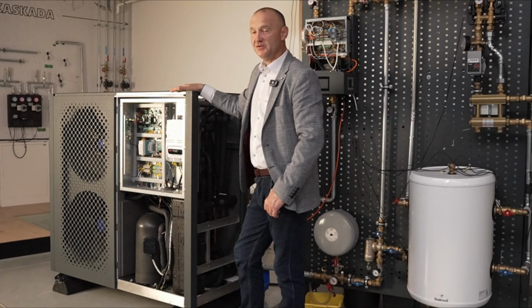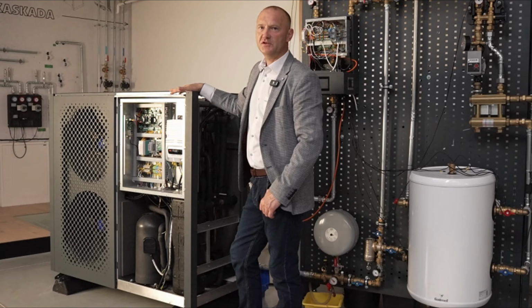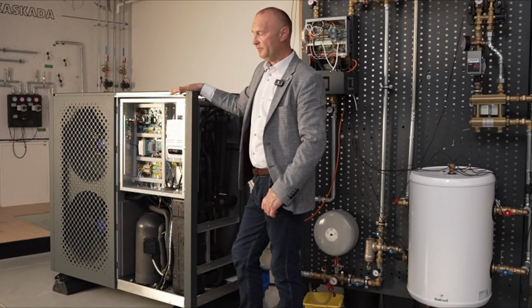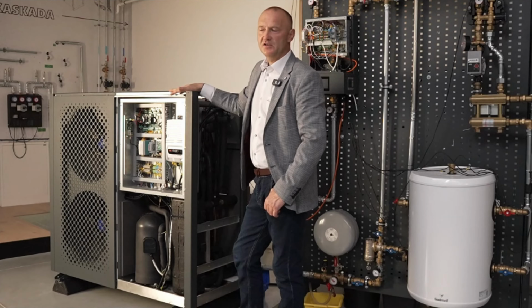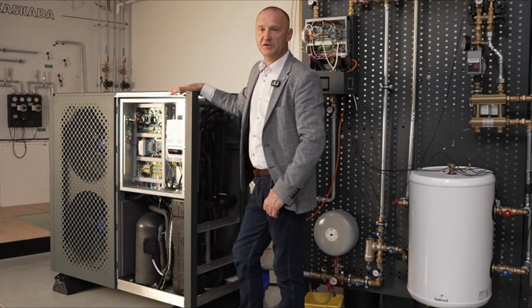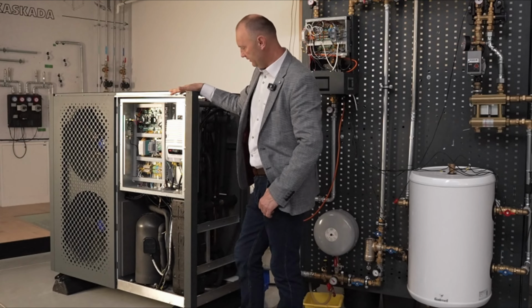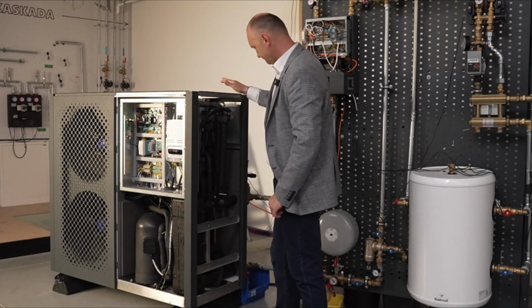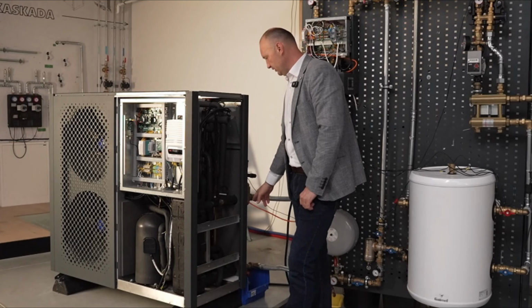And therefore, in our heat pumps, you can confidently use glycol solutions if you so wish, specifically both ethylene and propylene glycol solutions. We don't impose any restrictions here. We know there are heat pumps on the market where after glycol is poured in, the heat exchanger can even dissolve. That's not the case with us. On the water circuit, here we have the inlet.